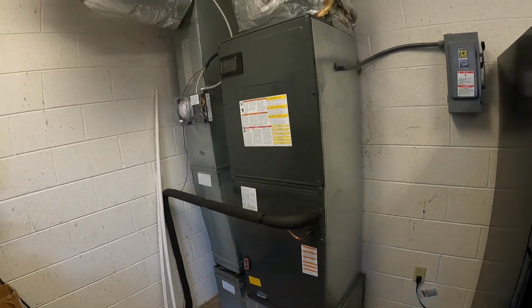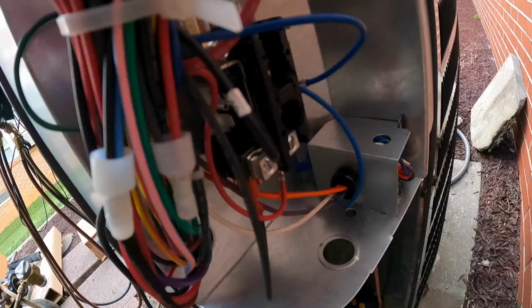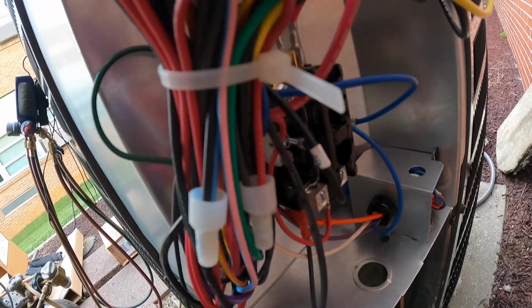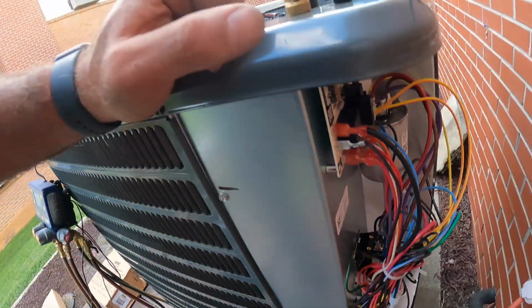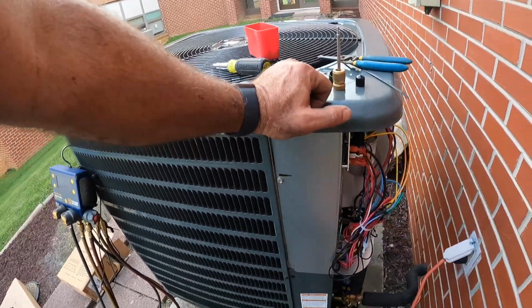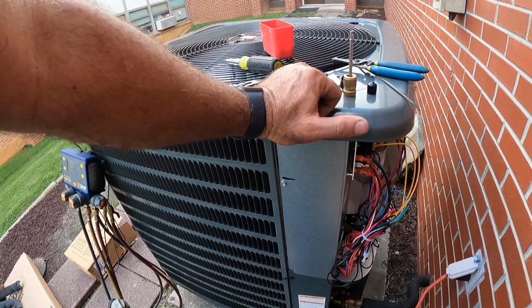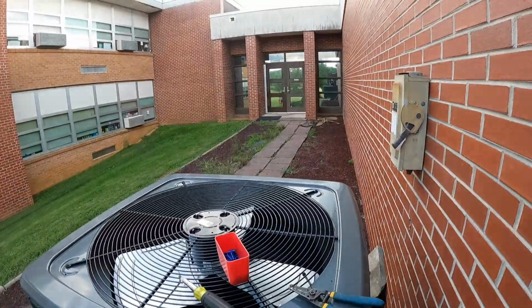I'm going to go out and see if it tried to pull the contactor in. The contactor is not pulled in at this point, at least. Like I said, it may have a longer delay on the compressor than it does on the fan with the built-in control. But what I'll do is run inside there.